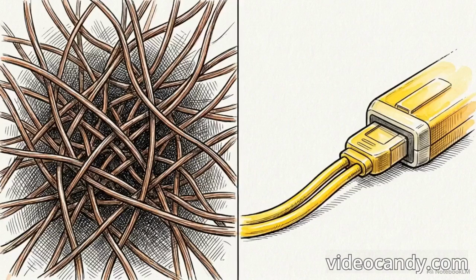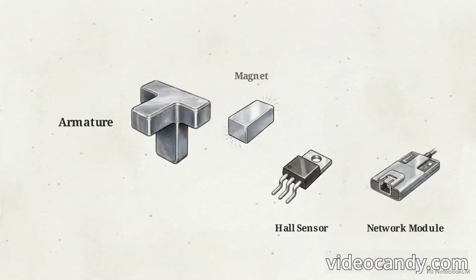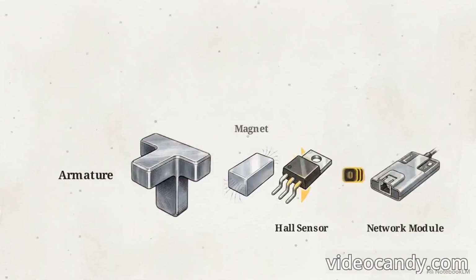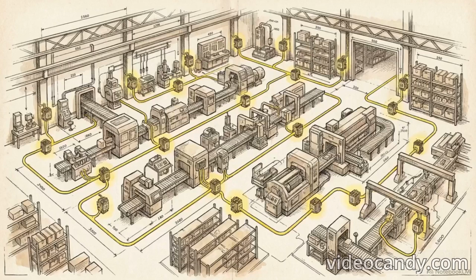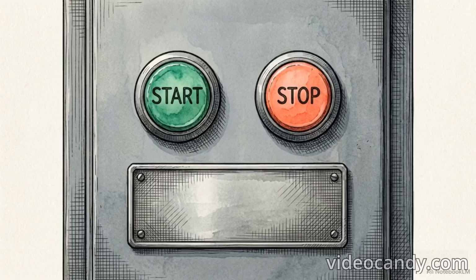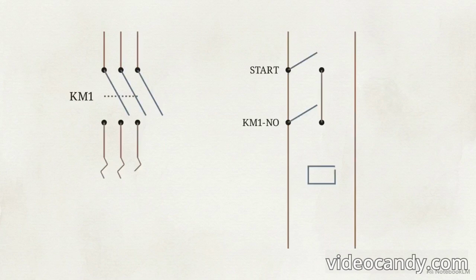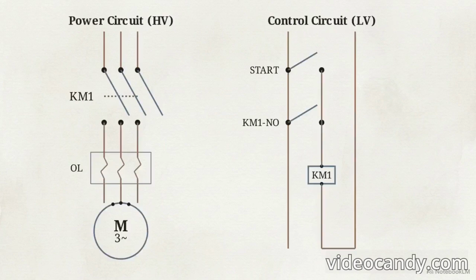By snapping solid-state electronic relays or pneumatic timers, like items 7 and 10, directly onto the unit, engineers embed timing logic locally. The networking layer is managed by snap-on modules, like the AS interface, which replace discrete copper runs with a serialized data bus. These modules use Hall sensors to monitor the physical position of the armature and translate that state into digital telegrams. This allows a single 2-wire cable to carry the specific start commands and status confirmations for up to 62 individual motor starters. These modular frameworks transform the physical switch into an intelligent, networked node within the facility's control hierarchy.